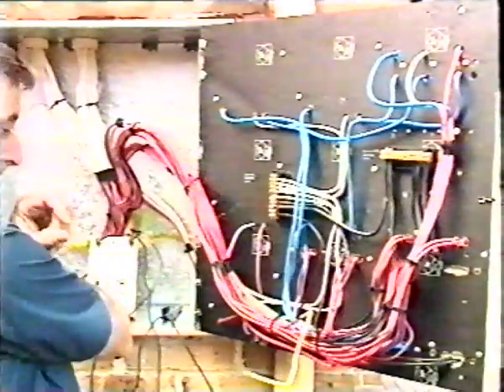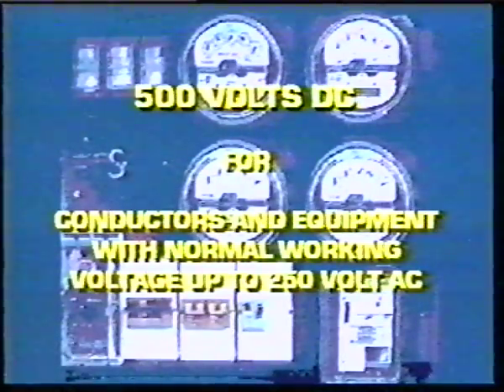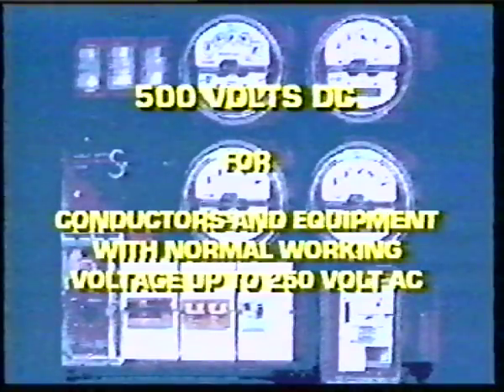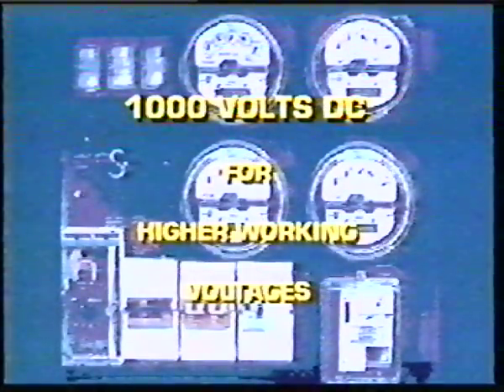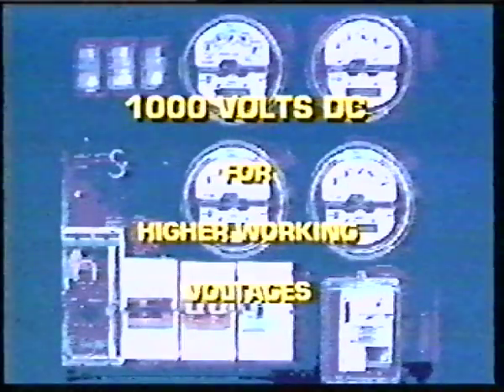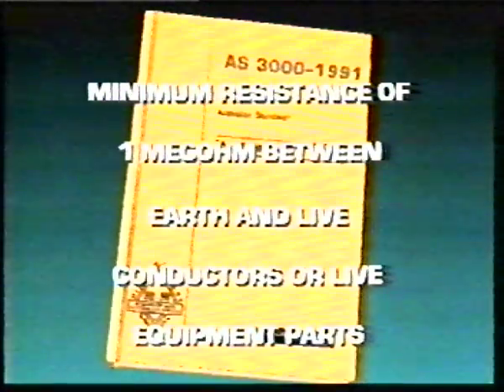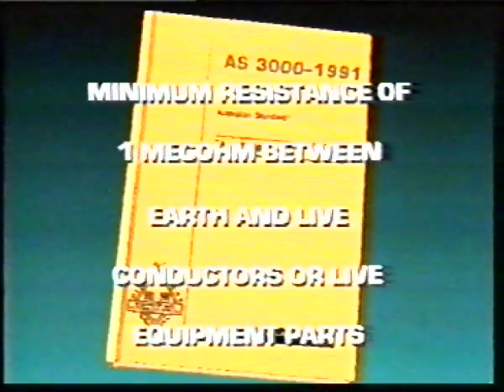These tests are necessary because all live conductors, including neutrals and live equipment parts, must be insulated to prevent electric shock hazards caused by inadvertent contact, fire hazards from short circuit, and equipment damage. We test the integrity of the insulation by stress applied by direct current at the following voltages: 500 volts DC for conductors and equipment with a normally working voltage up to 250 volts AC, and 1000 volts DC for higher working voltages. The requirements of the AS3000 are generally a minimum resistance of 1 megohm between earth and live conductors or live equipment parts.